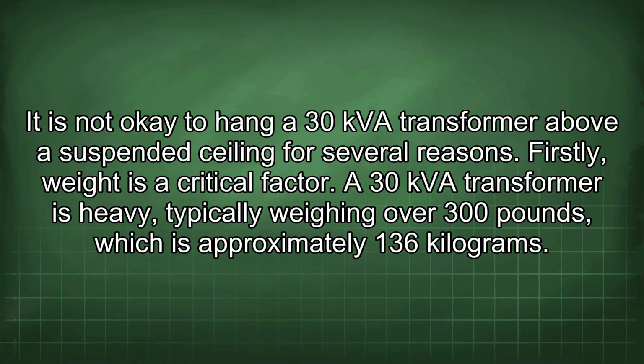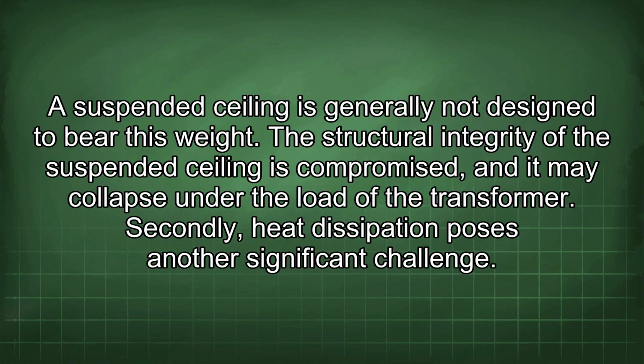It is not okay to hang a 30 kVA transformer above a suspended ceiling for several reasons. Firstly, weight is a critical factor. A 30 kVA transformer is heavy, typically weighing over 300 pounds, which is approximately 136 kilograms. A suspended ceiling is generally not designed to bear this weight. The structural integrity of the suspended ceiling is compromised, and it may collapse under the load of the transformer.